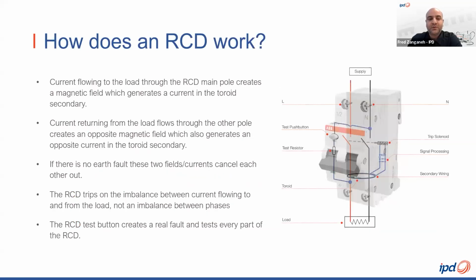Great. So now that we know what this RCD is standing for, how does an RCD work, Ian? It's pretty simple, really, Fred. The current flowing to the load runs through the RCD main poles, as you can see on this diagram. And this creates a magnetic field which generates a current in the toroid that the main pole is passing through. The circuit is completed when the current returns from the load and flows through the other pole. So both of those pole currents will flow through that toroid. This creates an opposing magnetic field, which also generates an opposite current in the secondary, the toroid.